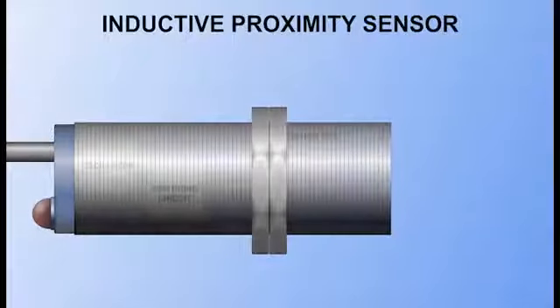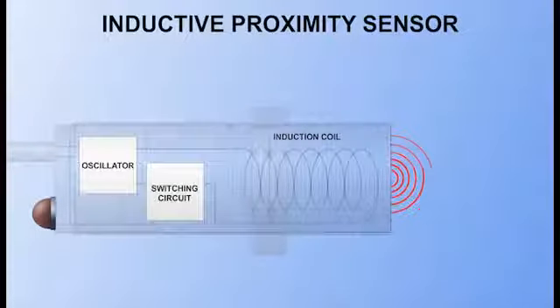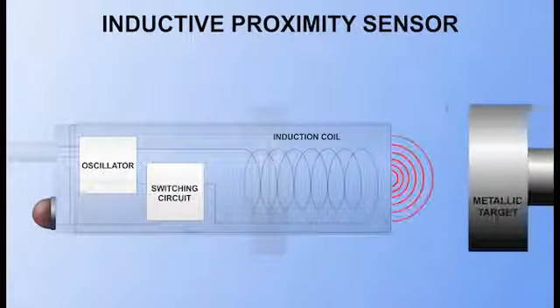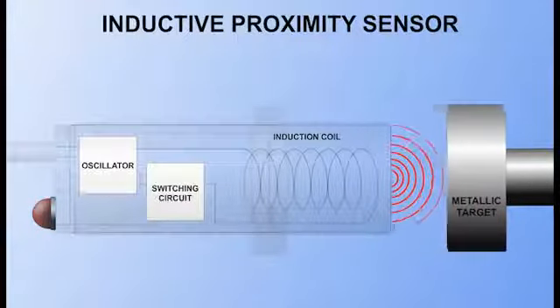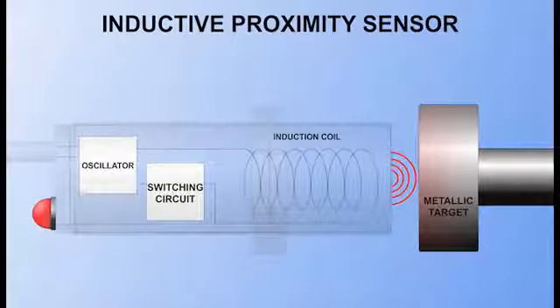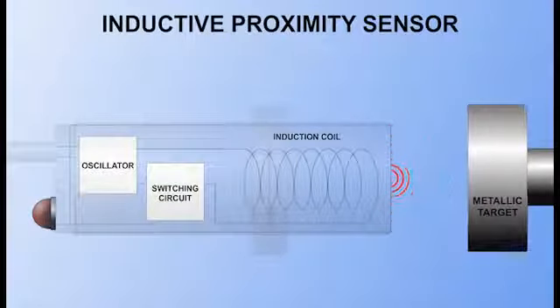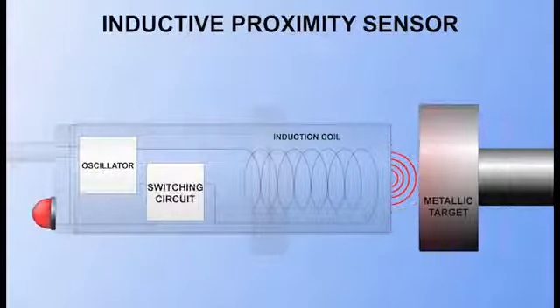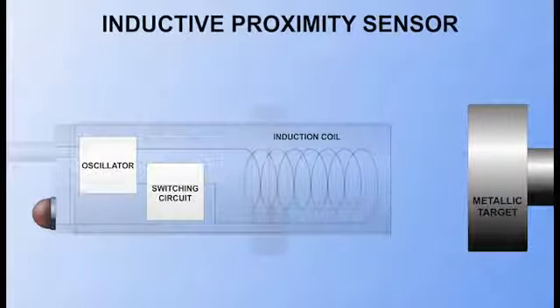Inductive PROX sensors are designed to emit an oscillating magnetic field. When a metallic target enters the field, the target absorbs some of the field energy, and the oscillations stop. This action triggers a switching circuit connected to the controller. Thus, when a target is sensed, the controller receives a signal that the target is in place.